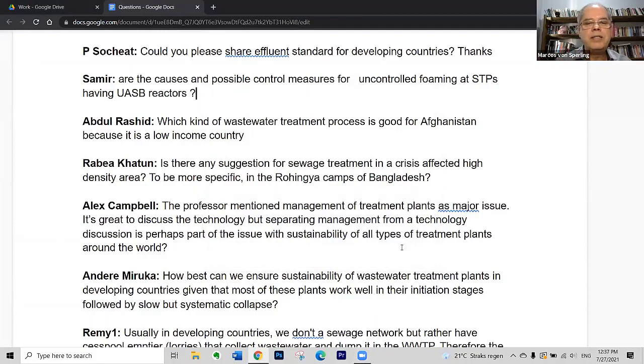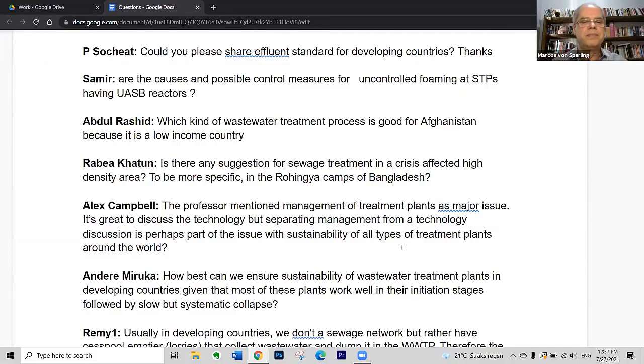If we are discussing scum, that's a major problem because scum can build up inside the UASB reactor — which is a closed reactor — and can even destroy the tri-phase gas-liquid-solid separator. My colleague Carlos Chernicharo is studying automatic removal of scum, because it's not simple — you cannot just open a gate and expect scum to move toward it. With a large reactor, using a hose is not feasible, so hydraulic-based removal methods are being explored.